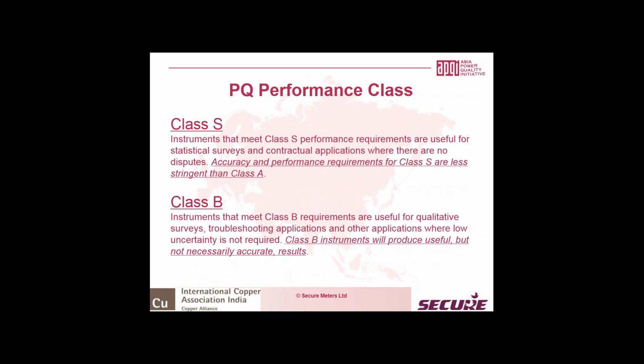The standard itself says that class S instruments are useful for statistical survey and contractual applications, whereas class B are primarily for qualitative surveys, troubleshooting, and not usually recommended for in-circuit applications at critical loads or critical installations.